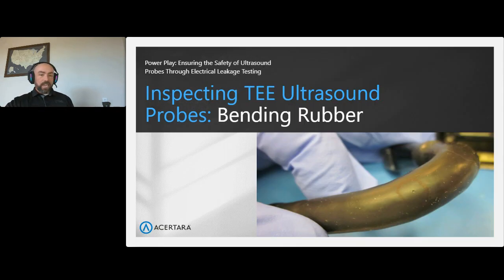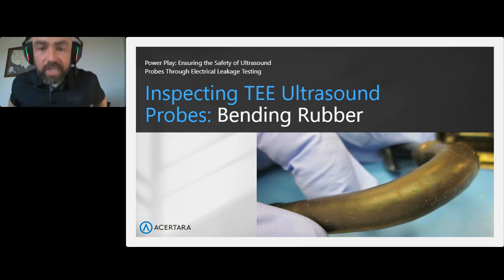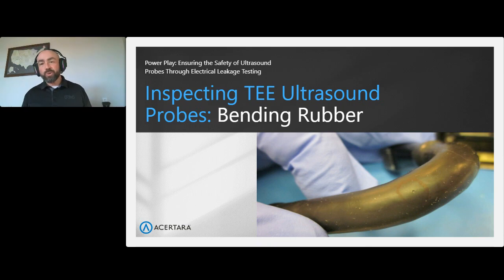Looking closer at the actual TEE probe, the bending rubber, the articulation sleeve, you can see the circled portion there in the middle. That's a hole where disinfecting fluid can get into the probe and destroy the electronics. That's a hole by which you could have cross-contamination, right? Nasty things living in there that you're going to pass from patient to patient. So it's important to inspect this portion because it does move. That's where you're going to see failures tend to congregate, in close proximity to that articulation sleeve or in the sleeve itself.